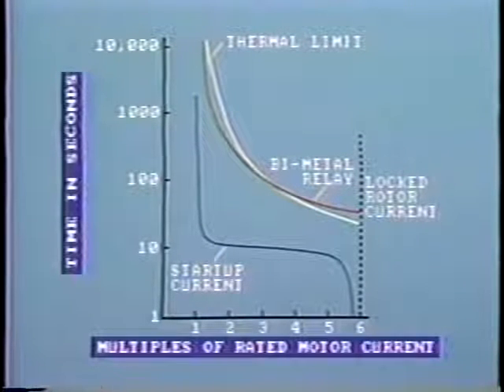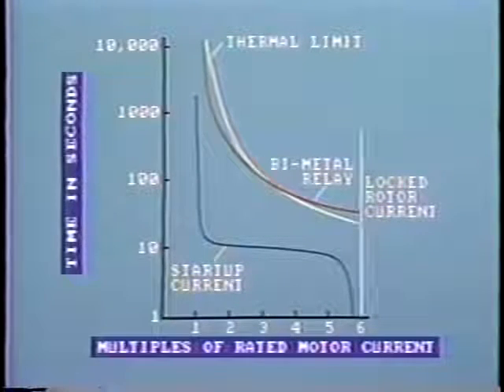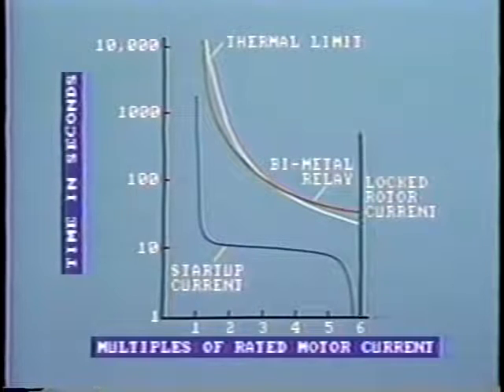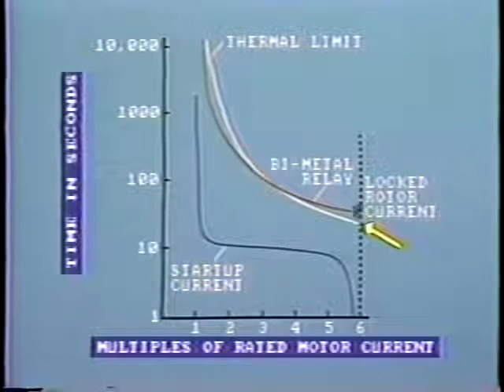However, it is quite impossible to get the curves to match exactly, and we will probably find that for high values of current, the bimetallic switch is too slow. For example, at this point, we show the current which the motor pulls when the rotor is stalled. This is the locked rotor position. We can see that if the motor failed to start, perhaps due to a mechanical problem, then the relay would trip some 20 to 30 seconds after the design limit was reached. This could result in serious damage to the rotor.